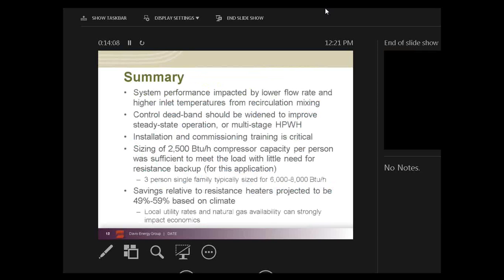So in summary, we noticed from monitoring that the system performance was impacted significantly by cycling. A lot of degraded performance from the cycling, especially during the summer when occupancy was low and there were a lot more parasitic losses. But it was also impacted by lower flow rates and the higher inlet temperatures from the recirculation loop. We suggested that either a deadband be widened or the controls changed some to improve and extend full load operation, but maybe even going to a 2-stage heat pump water heater would improve that performance.